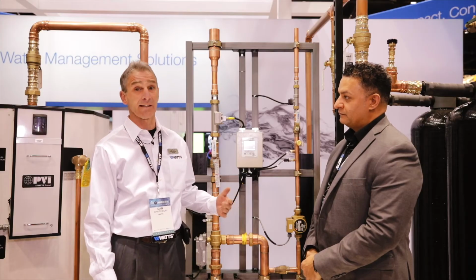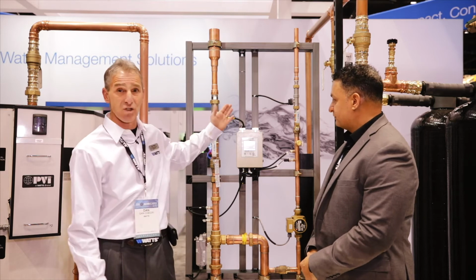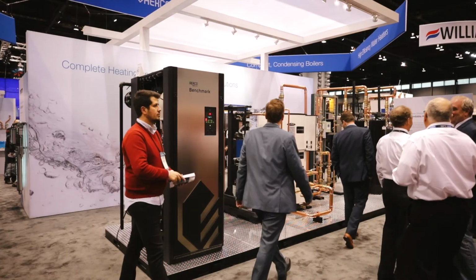You're going to have an inlet and outlet temperature and a pressure. You're going to have a return temperature and pressure. You're going to have a flow meter package on it. All that information is bundled and sent out to your BAS system. We have 3 languages that we can speak out of the box. It's the BACnet IP, BACnet MS/TP, and Modbus.